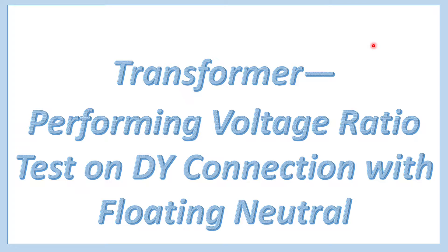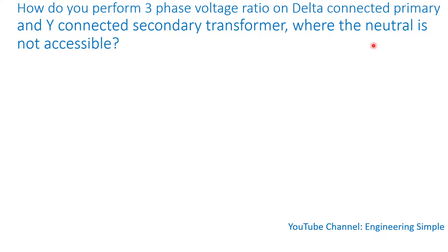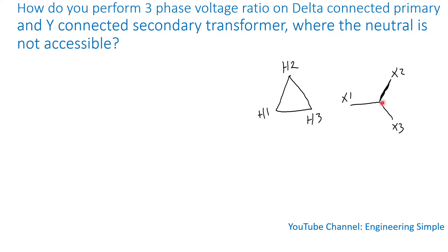In this video I'll talk about how to measure the voltage ratio for transformers connected as delta-Y, with the Y having a neutral not accessible. So you cannot measure phase-to-neutral voltage on the Y side. What we can do is perform a single-phase ratio, and there is a formula to convert from single-phase to three-phase ratio. Looking at the sketch to the right, you have the delta and the Y, with the neutral not accessible, so you can only measure line-to-line on the Y side.